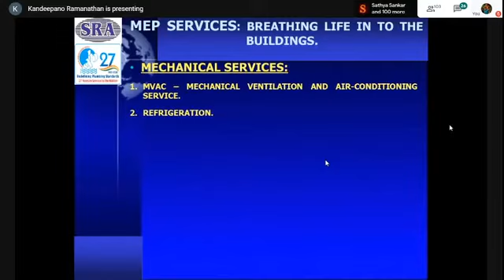Okay. Now the foremost of the mechanical services, number 1, is MVAC, mechanical ventilation and air conditioning services. Number 2, refrigeration, which is an allied service. Medical gas systems, which comprise oxygen, nitrous oxide, compressed air, medical vacuum, that is for suction, then AGSS, anesthetic gas scavenging system, and CO2 gas supply system. Even though they are all different gases by name, as a combination they are called medical gas, because in a hospital environment, all these gases are supplied at the same point in every room or operation theater wherever required. So design of these systems comes under mechanical services.